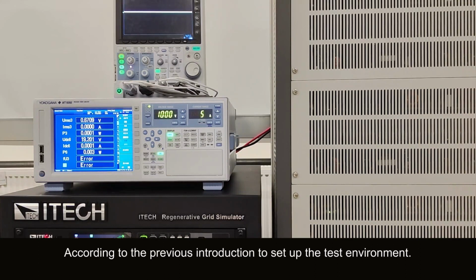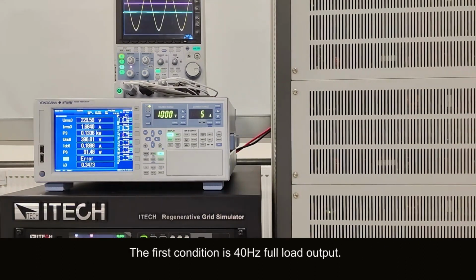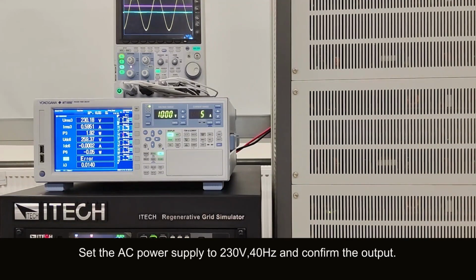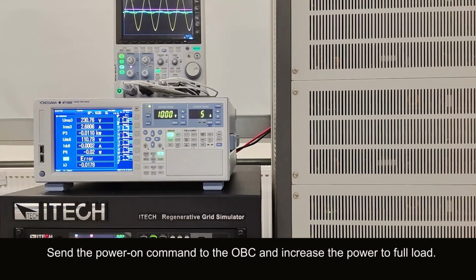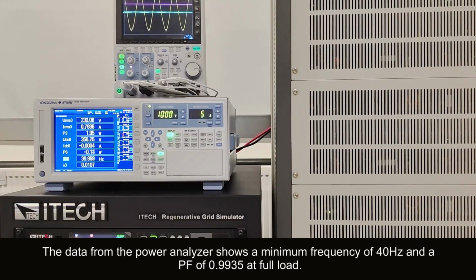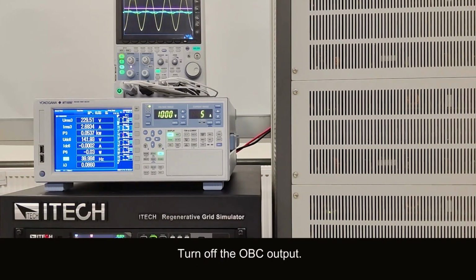According to the previous introduction, set up the test environment. The first condition is 40 Hz full load output. Set the AC power supply to 230V, 40 Hz and confirm the output. Send the power on command to the OBC, and increase the power to full load. The data from the power analyzer shows a frequency of 40 Hz, and a PF of 0.9935 at full load. Turn off the OBC output.